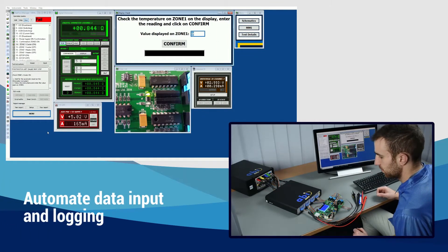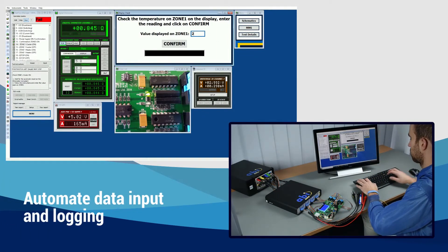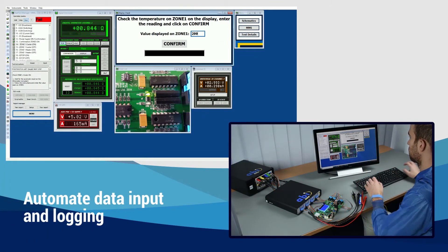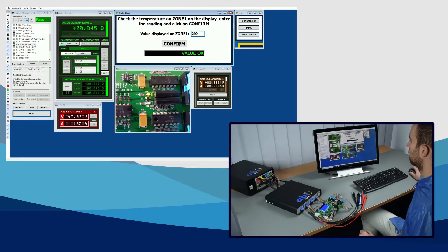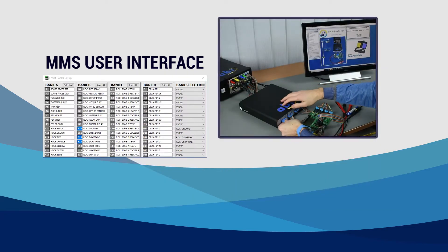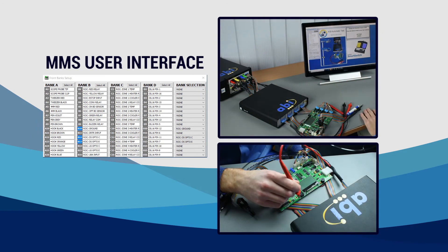Executing complex tests and completing data acquisition processes become much simpler. In each step, 16 unique paths can be created between the instruments connected to the rear of the MMS and the accessories, probes or test fixtures plugged into the front of the unit.